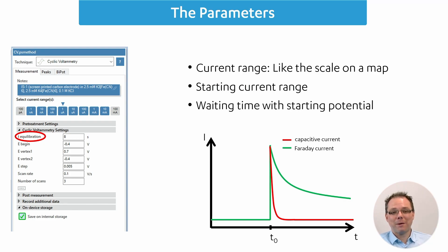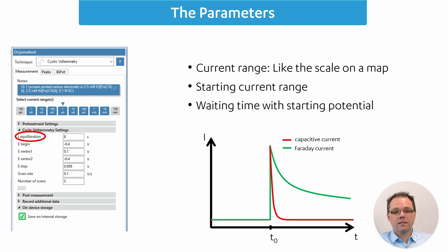The next parameter is T equilibration, which is a waiting time at the starting potential. We apply the E-begin — the starting potential — and do not record anything. One advantage is for autoranging: if you start a measurement and don't know if you've selected the best starting current range, you can set some T equilibration. Every half second, the potentiostat will switch the current range, giving it time to find the right one.